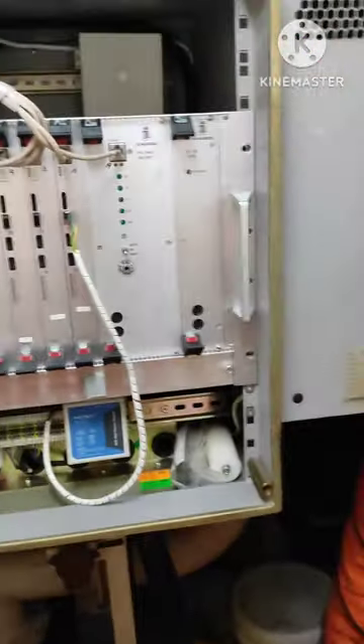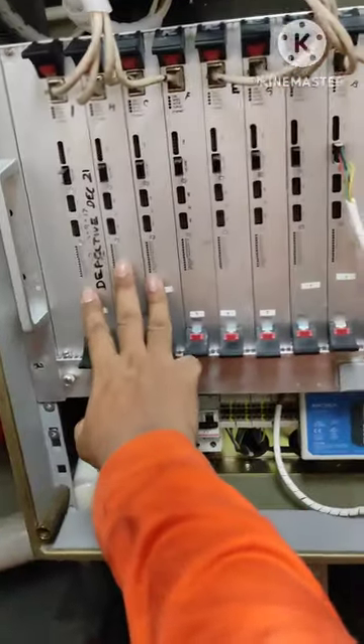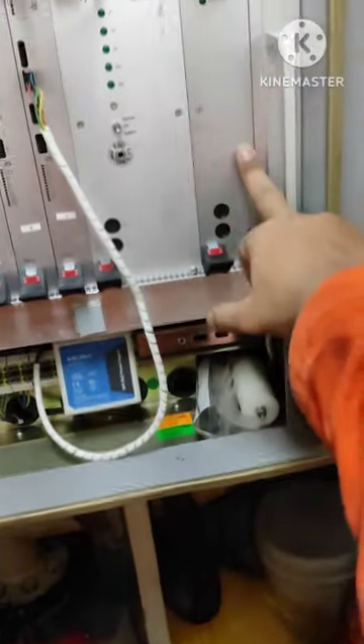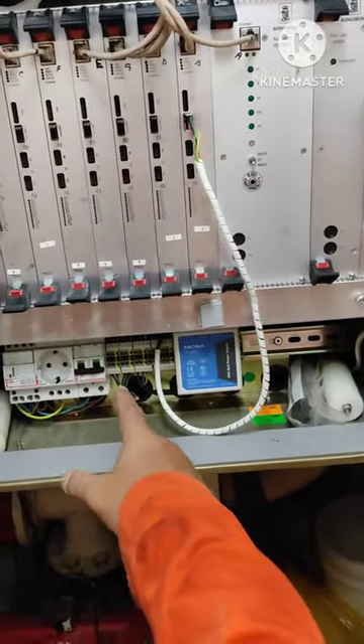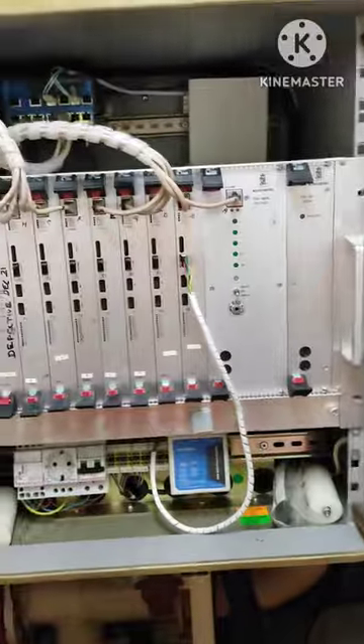Power card changed — all the defective ones are on the left side and the good ones are on the right side. We are going to connect now. Everything is back in place: three defective cards on the left side, five good cards on the right side. This unit is changed. We are going to put this breaker on and see the results — hopefully this will work now.